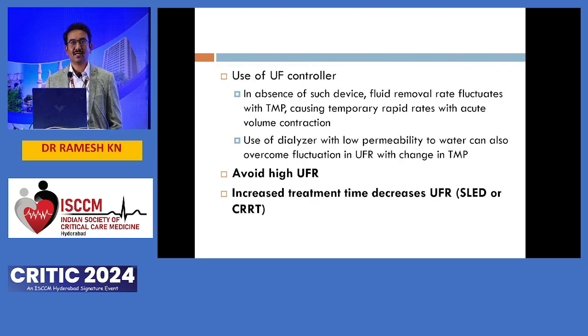And second is the ultrafiltration controller. Ultrafiltration, fluid removal, and intravascular depletion also depend on the transmembrane pressure. If there is a variation in the transmembrane pressure, that is hydrostatic pressure, then sometimes with the ultrafiltration rate, patients are more prone to hypotension or intravascular depletion. So we can use an ultrafiltration controller, which will modify that in the machine. We can also use low permeability membranes, which will not permit free flow of water, so that intravascular depletion will not occur.